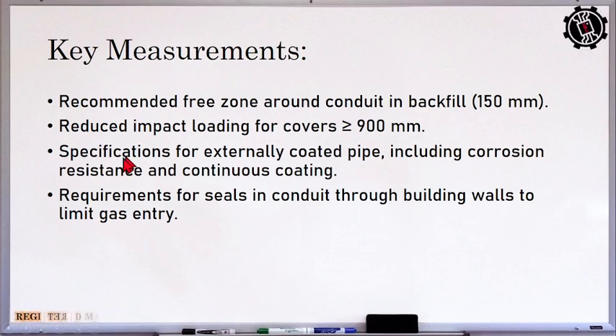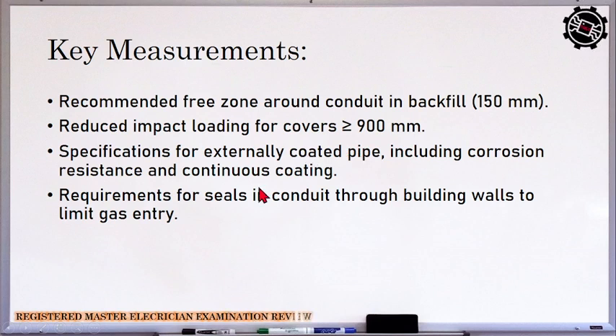Yun, so key points. So the recommended free zone for conduit in backfill is 150 mm. The reduced impact should cover greater than or equal to 900 mm. So the specifications for coated pipe must include corrosion resistant and yung kanyang coating is continuous throughout the whole pipe or the whole conduit. Then this must be seal, no? May seal yung ating conduit, no? Joints if those conduits are going through walls to limit the entry of gases.